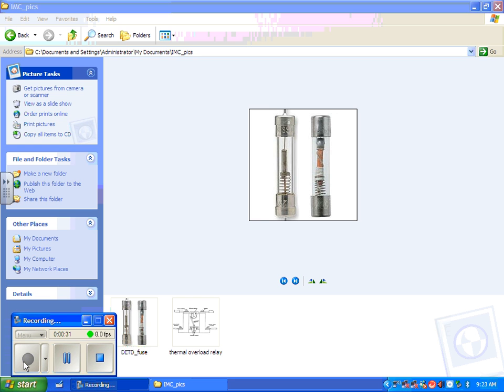And I know you've all read this, so it shouldn't be anything new to you, but I want to go over some essential information. I've said before that there are certain fuses that you can use for both the overload protection and the branch circuit protection. They're called dual element time delay fuses. You can sometimes protect the circuit and the motor with a dual element time delay fuse.